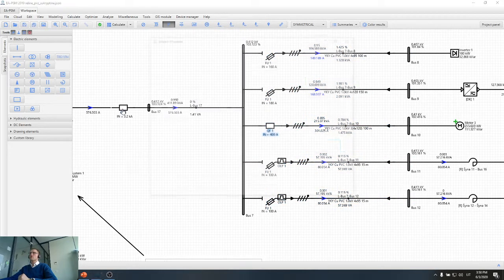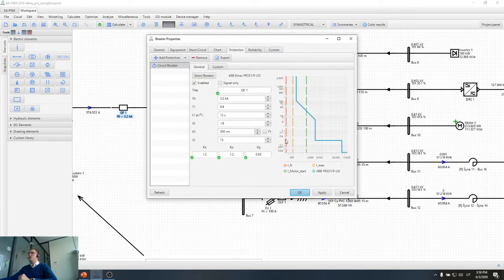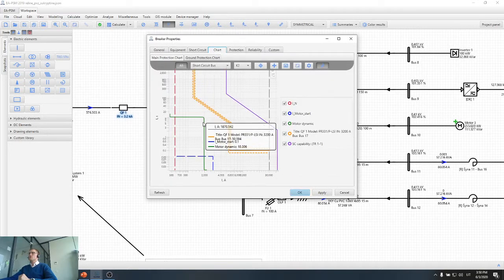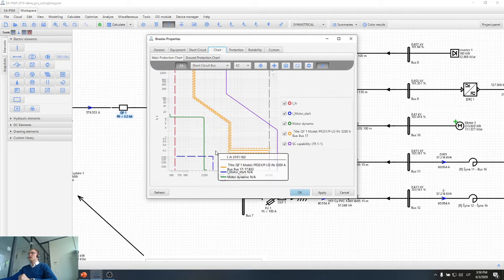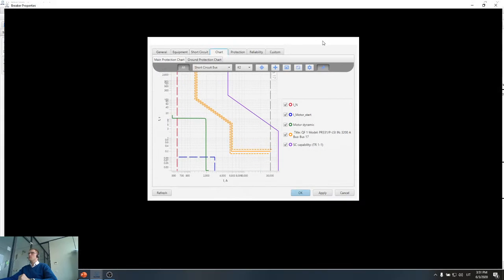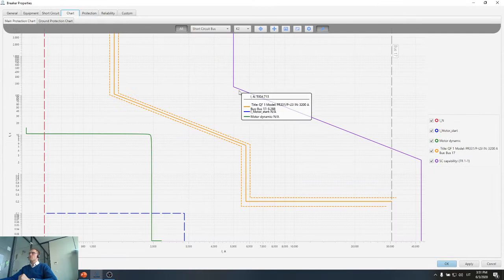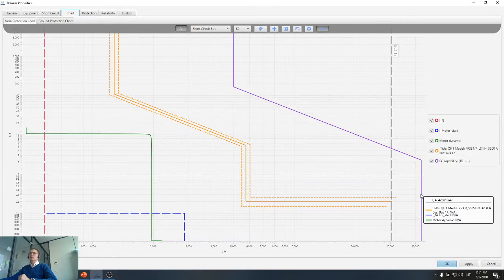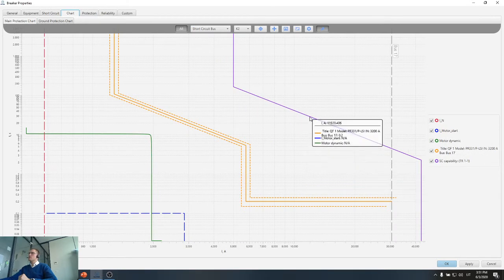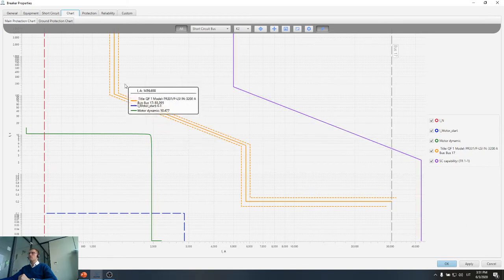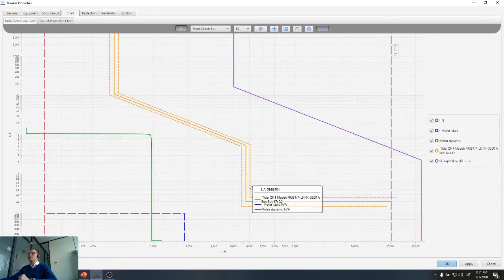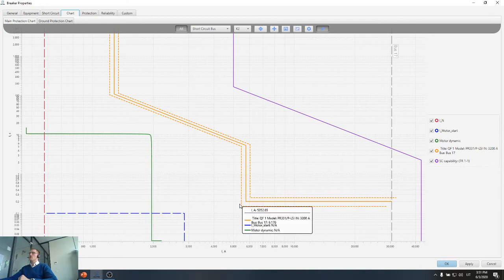So I will double click on the breaker here. Already settings for the breaker are provided. So the breaker won't trip during motor starting, and here we also have information about the transformer capability curve. You can definitely see that the transformer capability curve is bigger than our breaker chart, and therefore during short circuits our breaker will disconnect before the transformer will overheat.